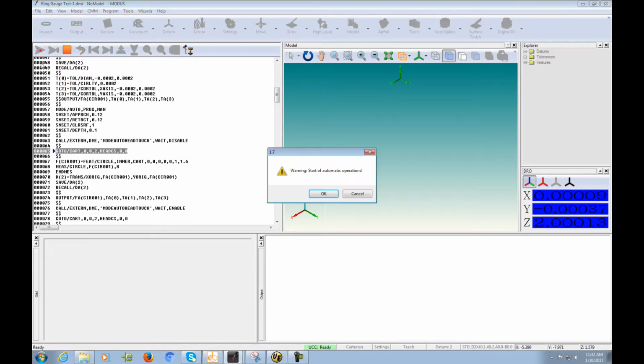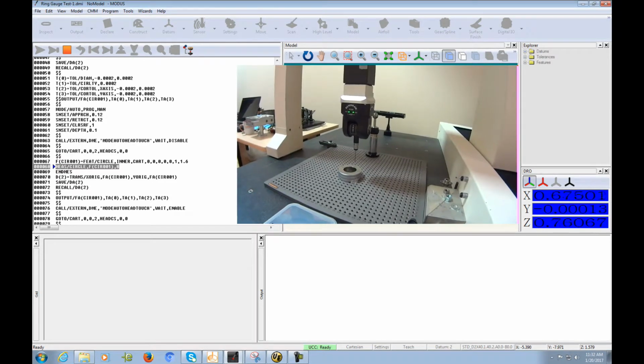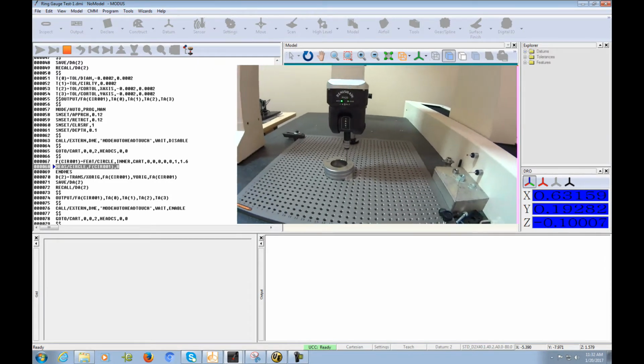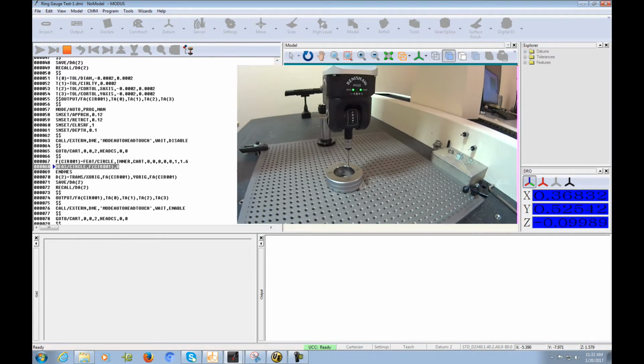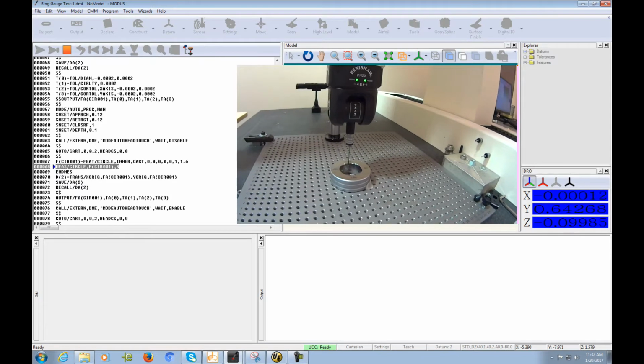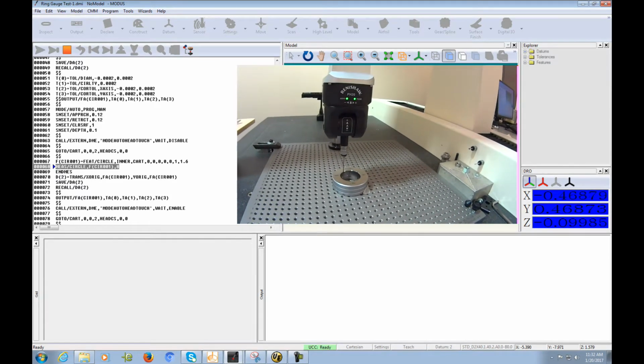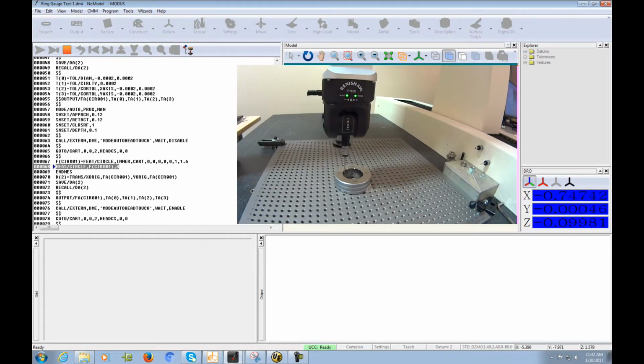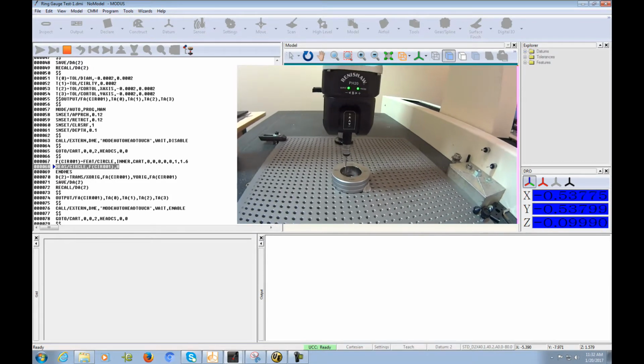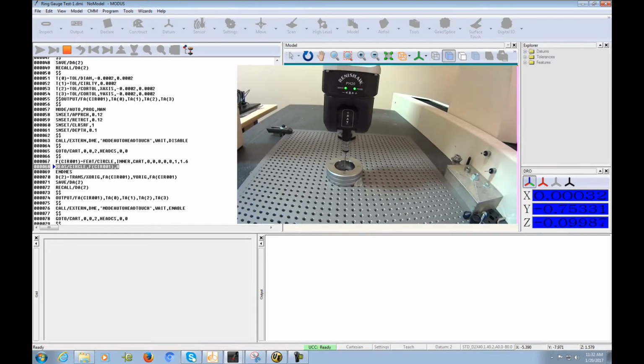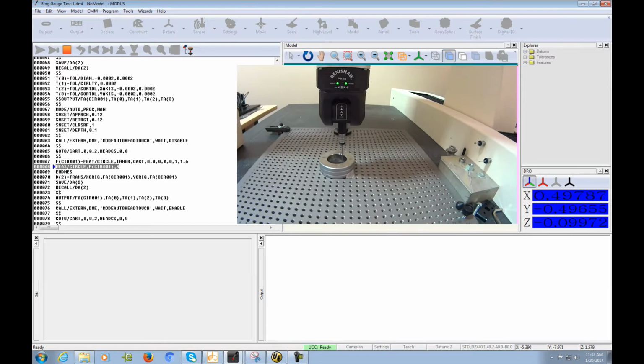So let's start directly from the DCC measurement. We got a warning and I'm going to click OK. Now you will see the first loop, the PH20 is measuring this gauge ring in a 3-axis movement, just like a PH10. It is measuring 8 points inside a 1.6 inch diameter and will report diameter, circularity, and X and Y coordinates.